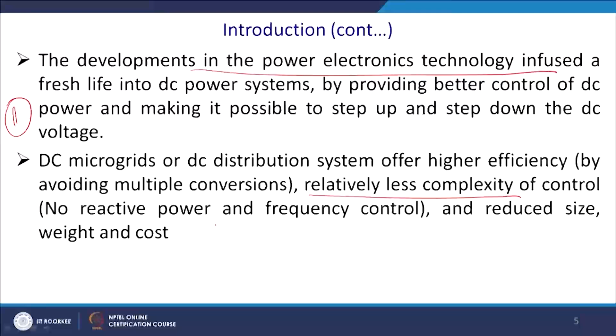And thus the microgrid or distribution system offers high efficiency by avoiding multiple conversions, relatively less complexity of control, and no reactive power and frequency control. Even in the AC system we have droop control where both voltage and frequency matter, because frequency is related to the real power and the voltage is related to the reactive power. In that way you require to control the PQ of the microgrid. But if it is DC, then that complex control is not required. You can only control the voltage and your requirement will be fulfilled. For this reason it is relatively less complex to control, with no reactive power and frequency control, and thus you have a reduced size, cost and weight.